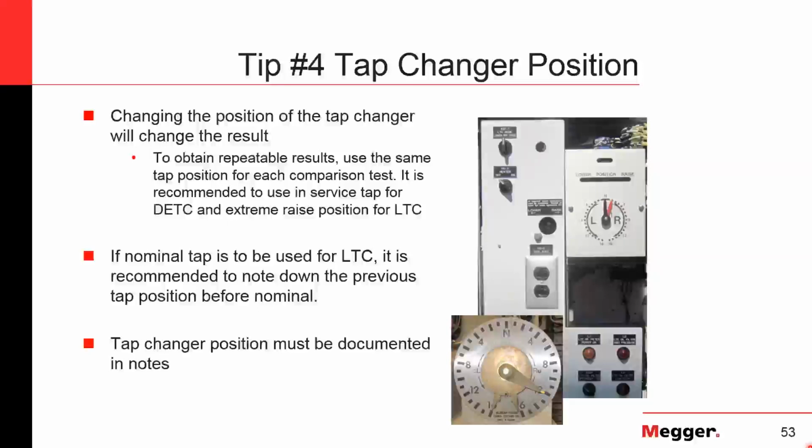So it's not necessarily that you'll know that A phase has hoop buckling and B phase has a collapsed winding. It's really that you see, okay, I have a winding issue with my transformer, so I need to go in and fix that winding, or there's an expected core problem, or there's a tap connection, and maybe my connection in my bushing is bad.